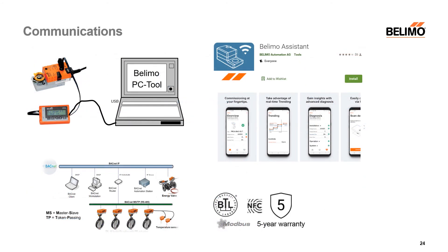Communication to your actuator is becoming an increasingly important topic. Years ago you would use a laptop with a cable to check run time, change the signal, etc. — this is still valid on many of our actuators today. With the PR, we take it a step further: it has NFC (near field communication) capabilities, where you touch your cell phone to the actuator to change signal, run time, do troubleshooting, and trending. The PR also has advanced communications with analog inputs for 2 to 10V, is BACnet MSTP and BTL certified, and also supports Modbus — covering key IoT technologies for your butterfly actuator.